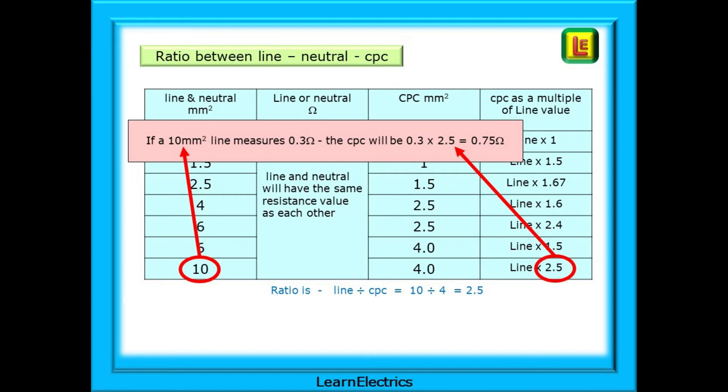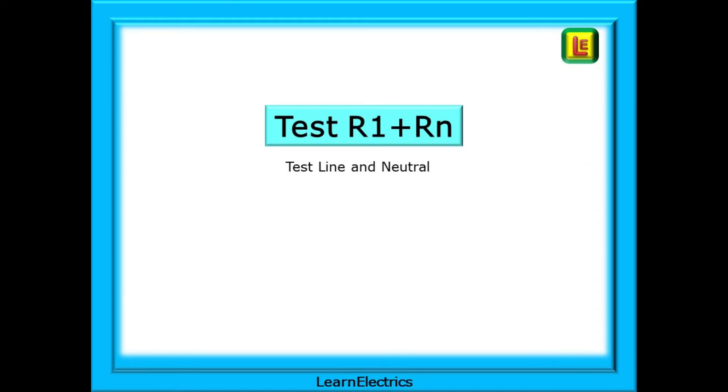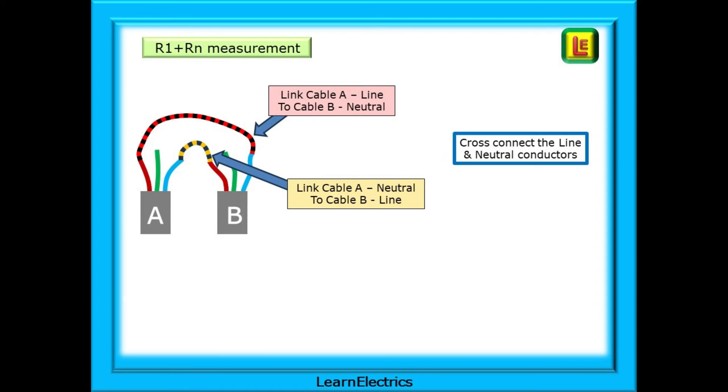Now we can test for big R1 plus big Rn, the effective resistance of the line and neutral as a parallel pair of conductors. We must cross-connect the line and neutral wires at the consumer unit. Using jumper wires, crocodile clips, choc blocks or WAGOs, link cable A line to cable B neutral. Then link cable A neutral to cable B line. Get them the wrong way round and the test results will be all over the place.